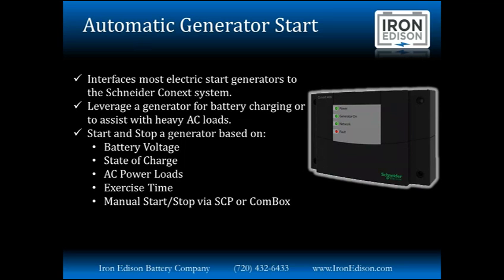The next accessory we're going to look at is the Schneider Automatic Generator Start. This is also known as AGS. The AGS is absolutely required for any system that's going to include an external fossil fuel powered generator. We have generators that we see that are powered by gasoline, diesel, propane, and other sources. So this auto generator starter AGS device is able to interface with almost every brand of remote start generator on the market today. Whether it's a 2-wire start stop, 3-wire, we have options for choke, for glow plug start, for diesel. Really, you name it. We have tons of different ways we can configure the AGS to start or stop the generator.